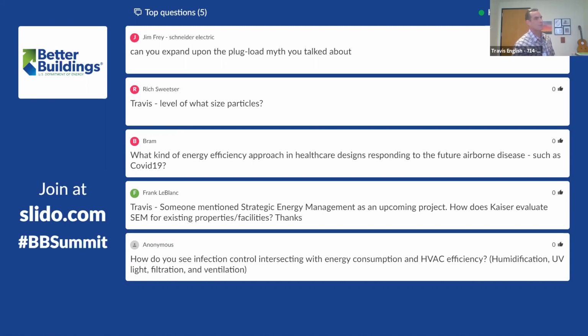Yeah, Shanti has been involved in some of this work, and I know some consultants on the phone have too. When I started here, we had design engineers in both the clinic buildings and the hospital laying in design assumptions around 2 or 3 watts a square foot—numbers like that, even for a patient room. At this point we've published papers about actual measured loads in surgery centers and throughout the medical office building. We worked with Shanti's group to publish stuff in hospitals, and Heather Burpee and her group in Washington have also published good studies. So that's what we tell design engineers now: don't look at the list of equipment, add up nameplates, and apply a diversity factor you made up—go look at the published studies and make sure your models match them.